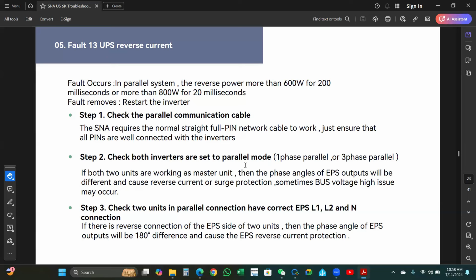Check both inverters are set to parallel mode, 1-phase parallel or 3-phase parallel. If both units are working as a master unit, then the phase angle of the EPS output will be different and cause reverse current or surge protection. Sometimes a bus voltage high issue may occur. Check the two units in parallel for the correct EPS line 1, line 2, and neutral connection. If there is a reverse connection of the EPS side of the two units, then the phase angle of the EPS output will be 180 degrees different and cause the EPS reverse current protection.